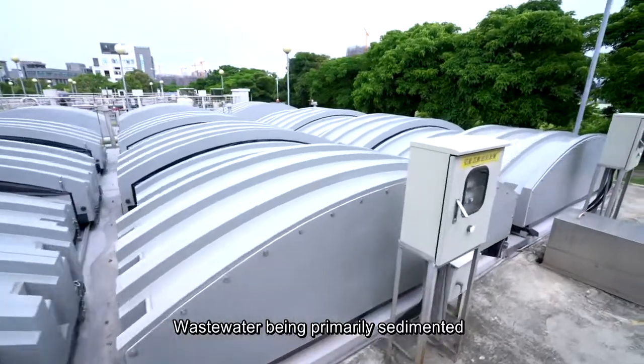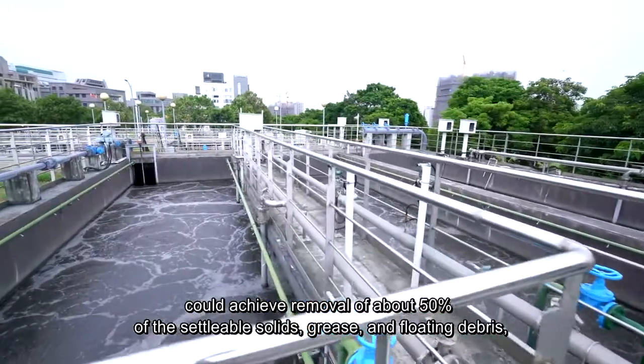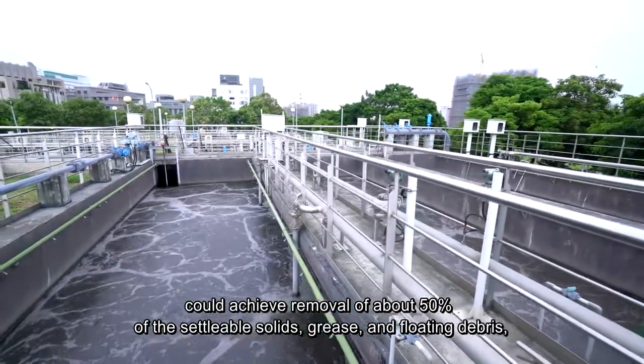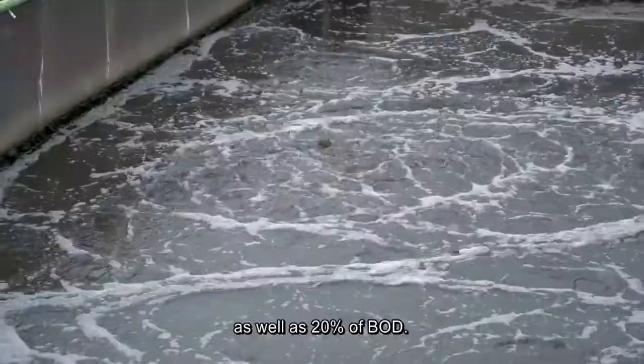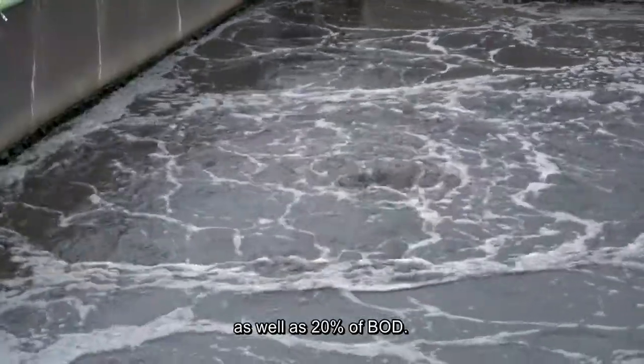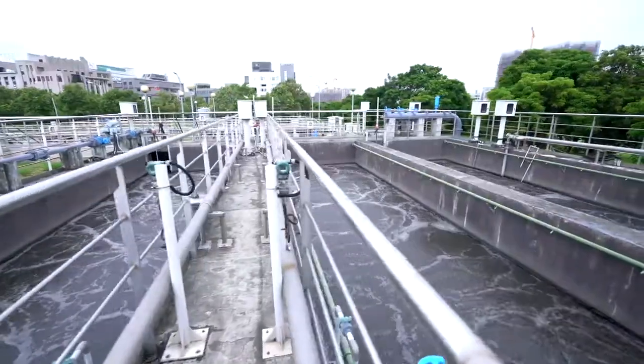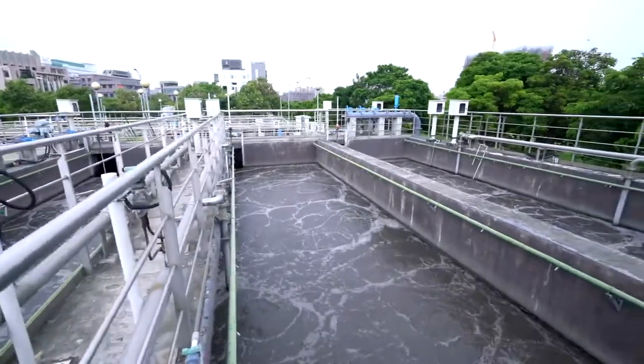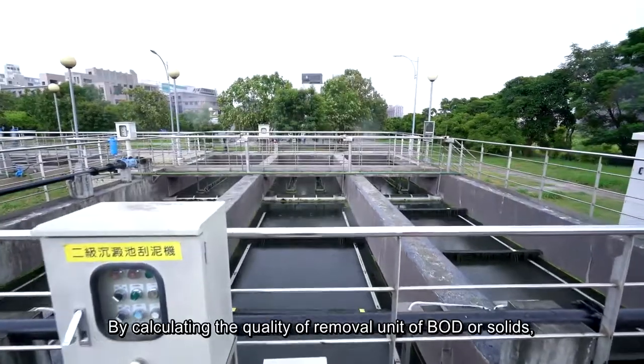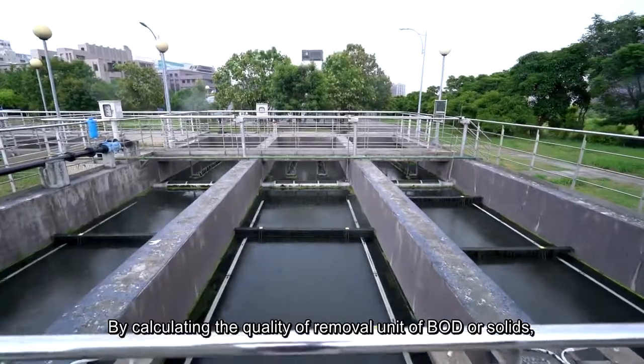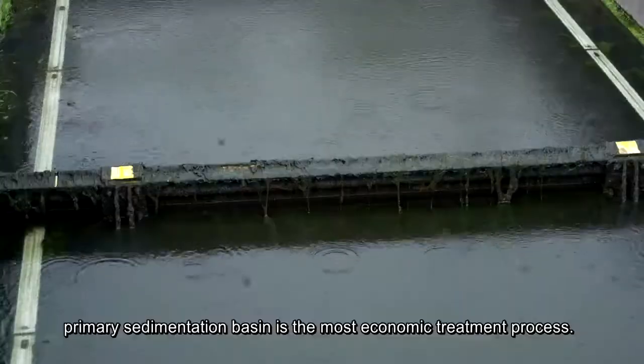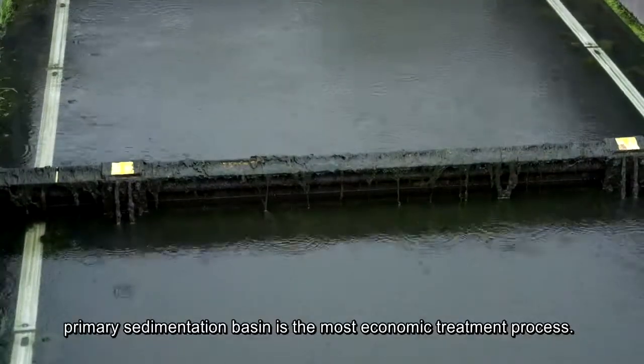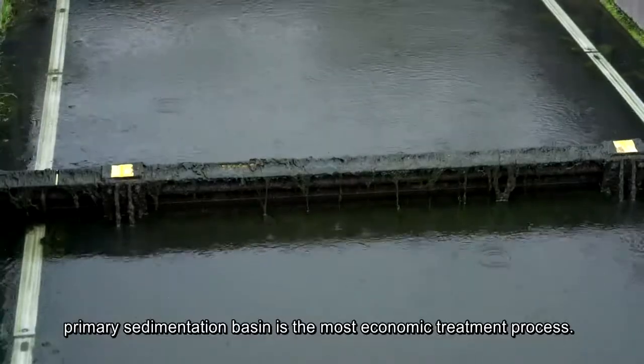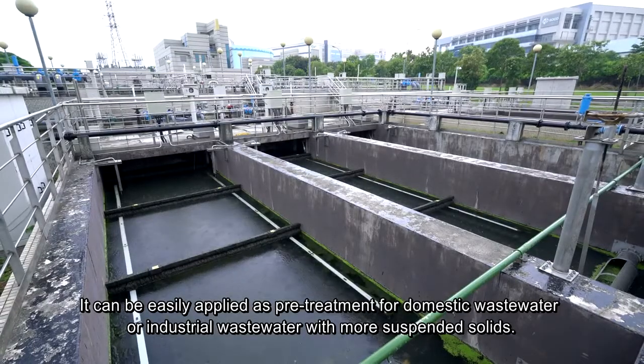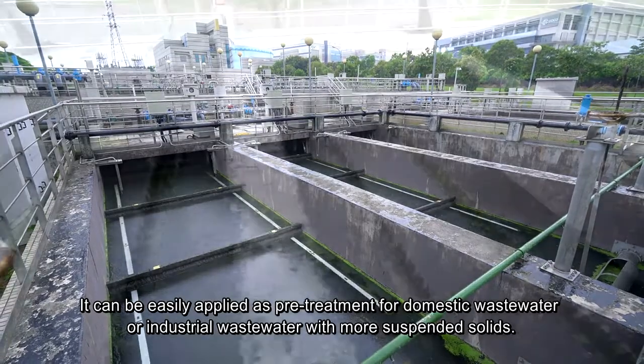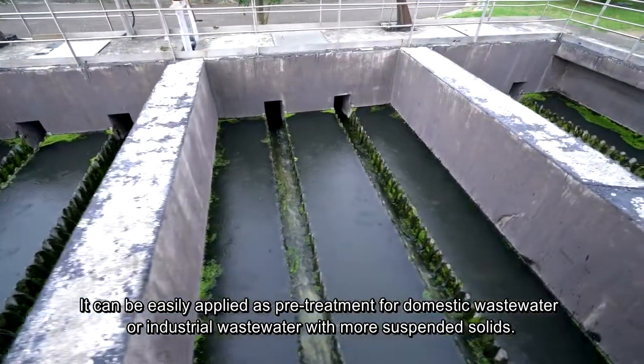Wastewater being primarily sedimented could achieve removal of about 50% of the settleable solids, grease, and floating debris, as well as 20% of BOD. By calculating the quantity of removal per unit of BOD or solids, the primary sedimentation basin is the most economic treatment process. It can be easily applied as pre-treatment for domestic wastewater or industrial wastewater with more suspended solids.